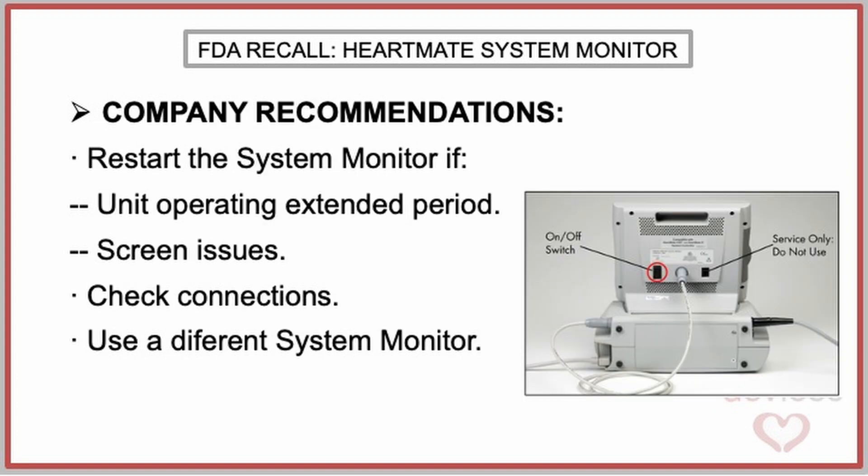The company recommendations are the following. Before connecting to the patient controller, restart the system monitor unit if the unit has been operating for an extended period, or if screen issues are noticed. To restart, turn off and then turn on the monitor using the on-off switch on the back. A complete restart takes about 10 seconds. The LVAD settings will remain unchanged if the unit is restarted while connected to the patient's controller. If screen issues persist after restarting, check that all cables and connections are secure and undamaged. If the problems continue, use a different system monitor.